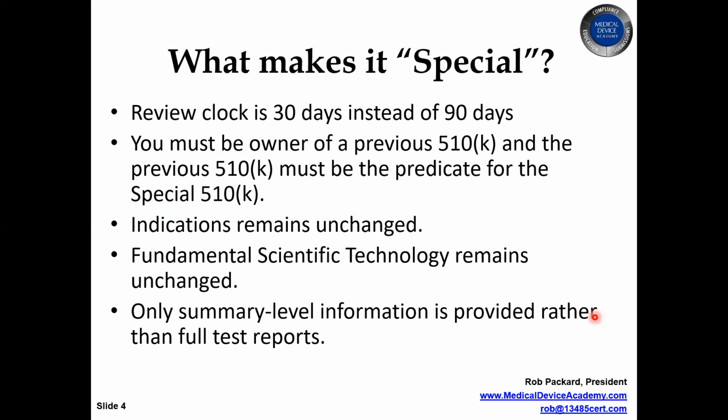Another thing that is required for special 510Ks is you can't change your scientific technology. So if your old device was using RF technology and your new device is using ultrasound technology, this isn't going to work. When you change the technology, even though the indication is the same, the new technology introduces new risks, and even though you could validate that it's safe and efficacious, that's not going to be a special 510K route. That's going to be a traditional 510K route or a completely new device classification.